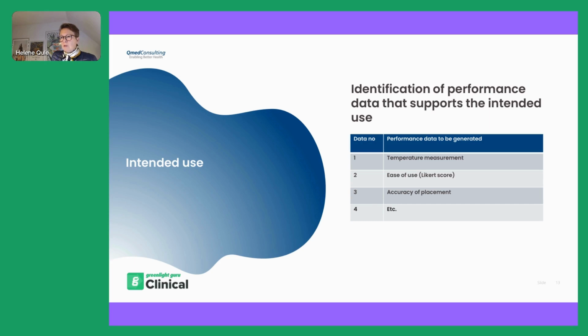The intended use is often a short statement that includes a general description of the device, including both the intended purpose and the intended users, the intended patient population, the medical conditions to be diagnosed, treated, and monitored, and other considerations. The principles of operation and the mode of action are normally also included, which is scientifically demonstrated if necessary. So the goal here is to define the data that needs to be generated from a performance perspective, to show that the product, when used according to the intended use, is both safe and performs. So what is it that the device actually does towards the patient?